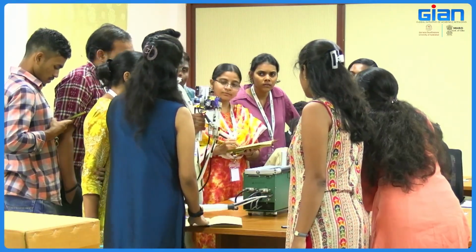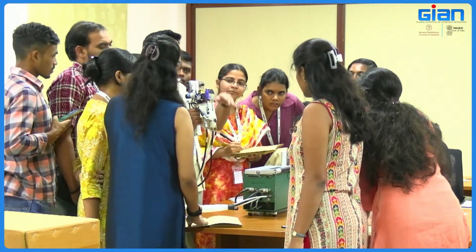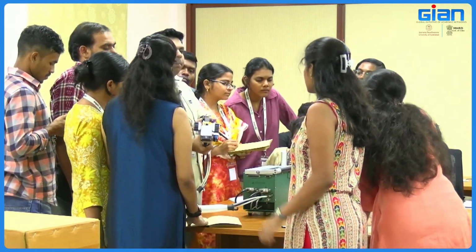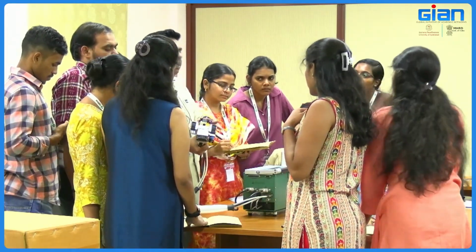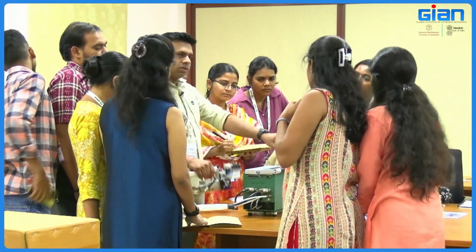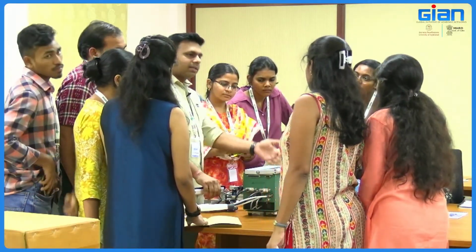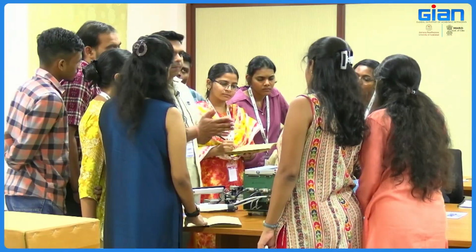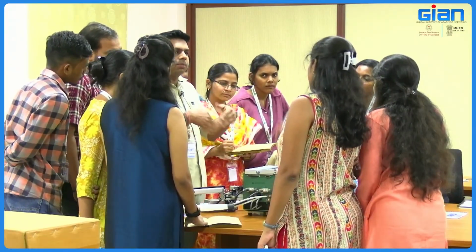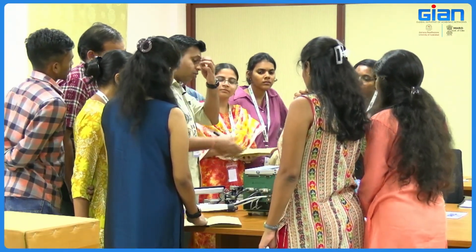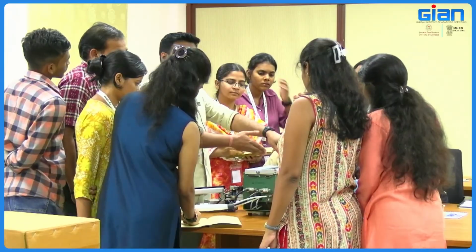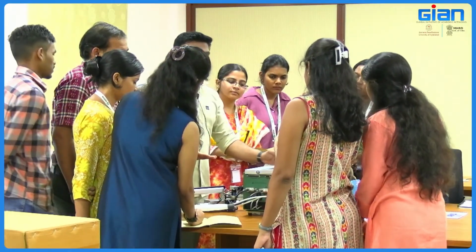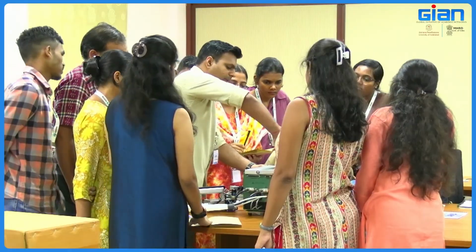So you see the sound, some click click sound came, right? This is the mixer. It will test whether the mixer is working or not. What happens if you use this CO2 cylinder is that it will mix this CO2 with some of the atmospheric CO2. It will not utilize everything. If it starts to utilize all the CO2 here, maybe it will not last more than 1 hour. That is the reason this CO2 mixer is used.